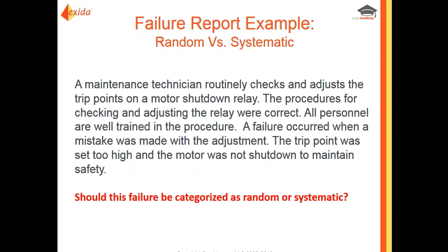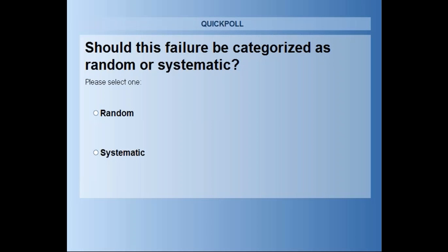Our second example: a maintenance technician routinely checks and adjusts the trip point on a motor shutdown relay. The procedure for checking and adjusting the relay is correct and all personnel were trained. The failure occurred when a mistake was made with the adjustment — the trip point was set too high and the motor was not shut down to maintain safety. Should this be categorized as a random or systematic failure?